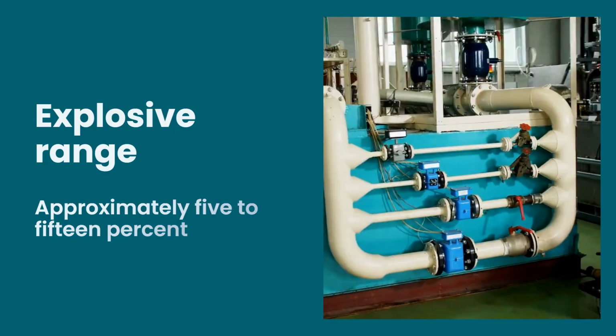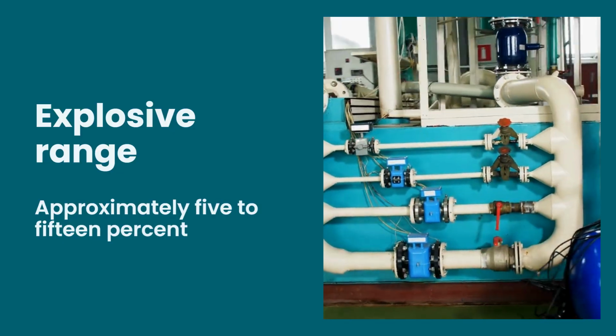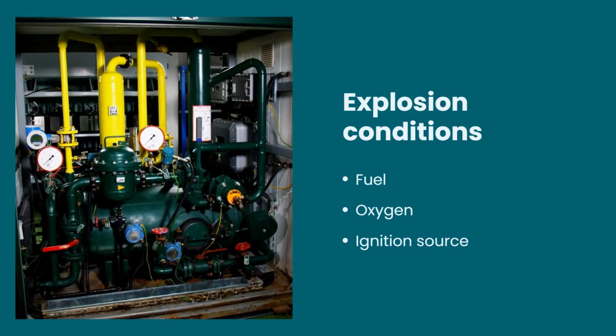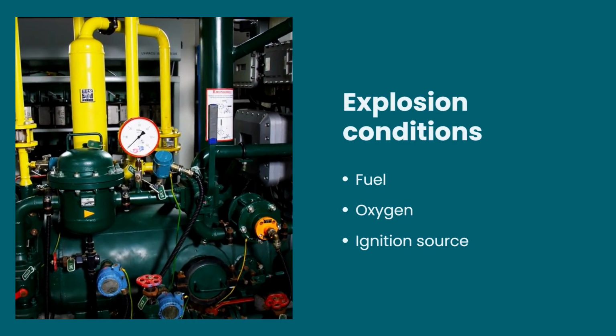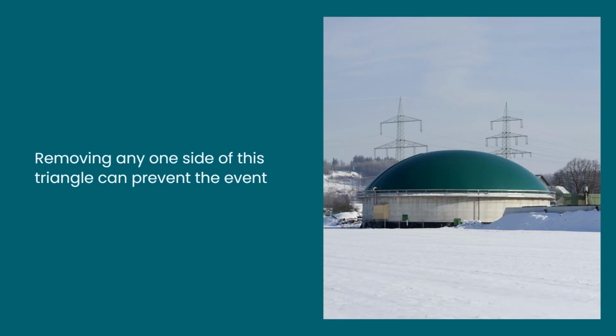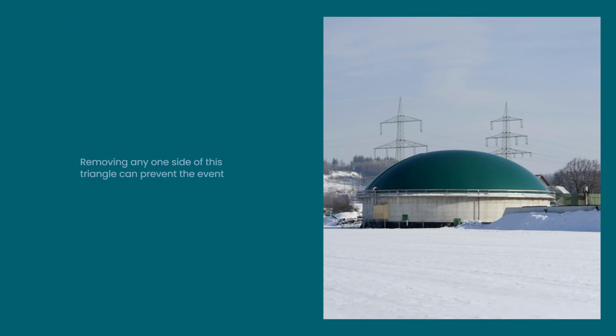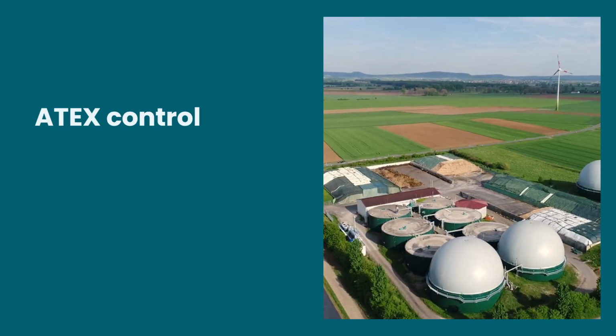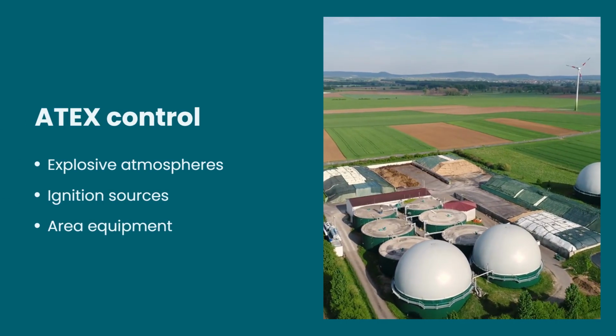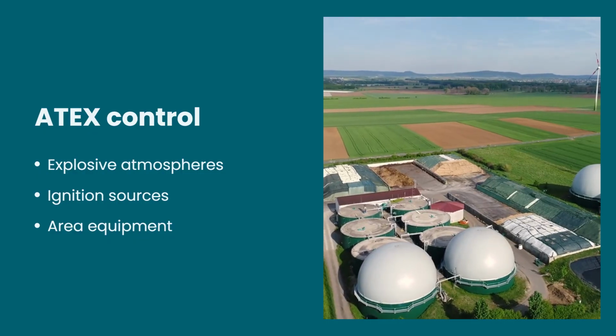Methane's explosive range in air is approximately 5 to 15%. An explosion requires fuel, oxygen, and an ignition source. Removing any one side of this triangle can prevent the event. ATEX requirements control explosive atmospheres, ignition sources, and equipment used in the area.